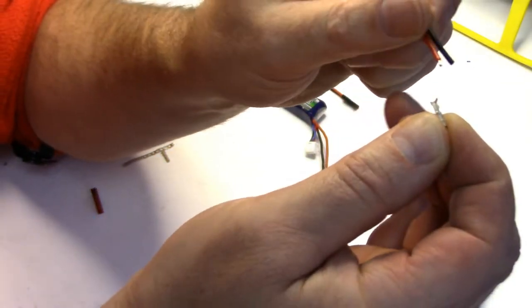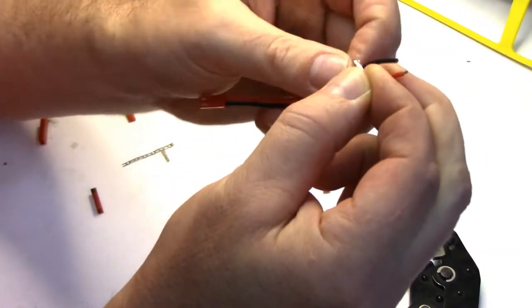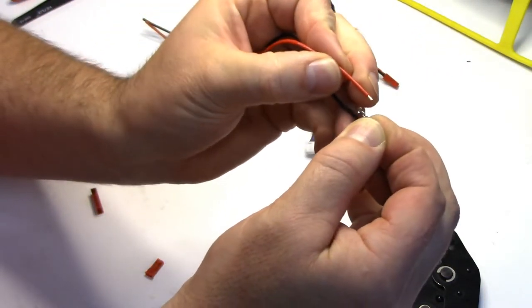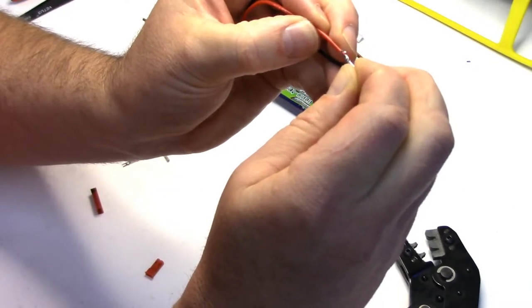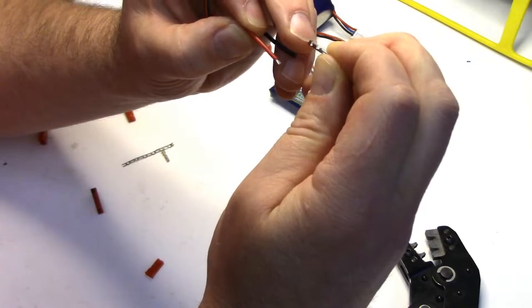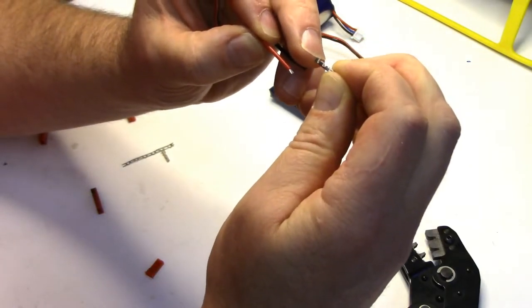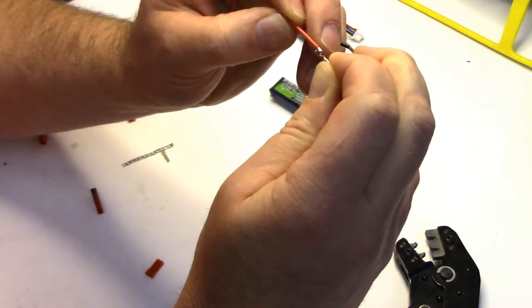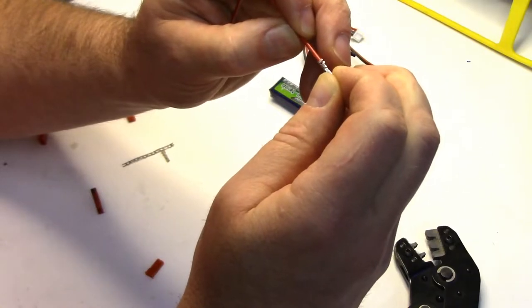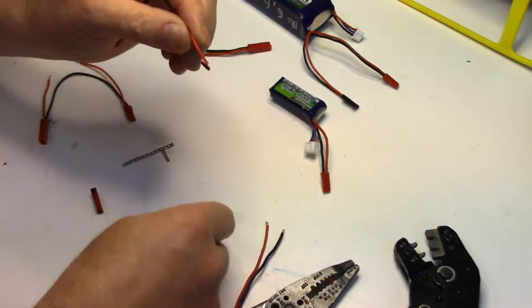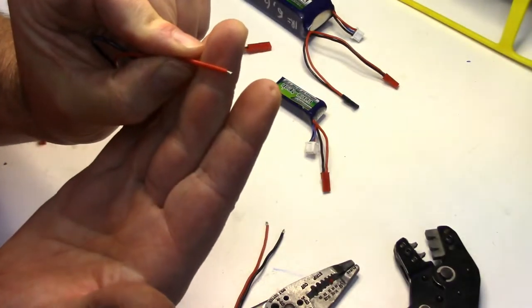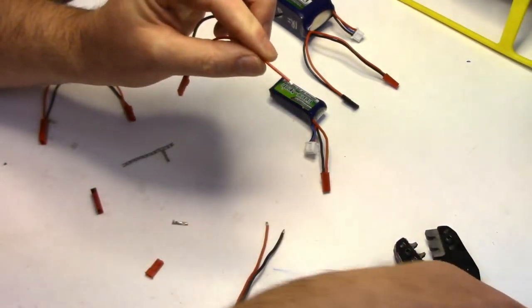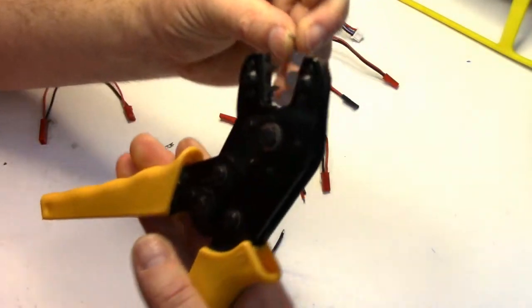You basically want enough wire exposed that it will just fit into the pin. This side of the crimp is actually grabbing the wire insulation and then the inner one crimps over the actual wire strands. So that's about three millimeters, just over an eighth of an inch that you strip off.